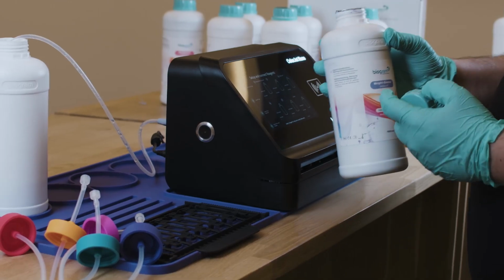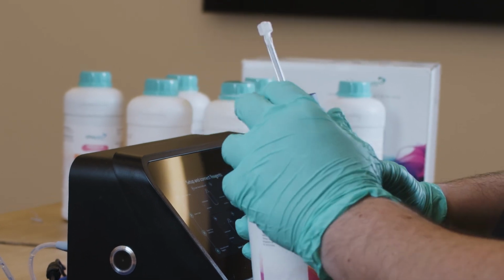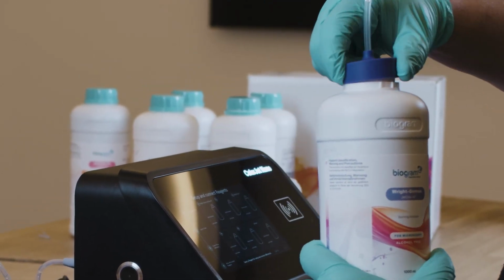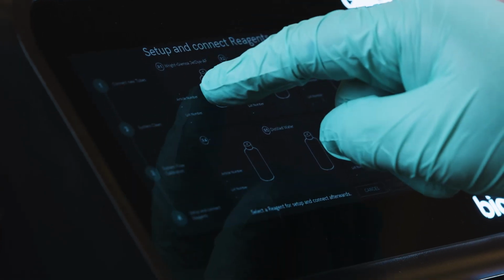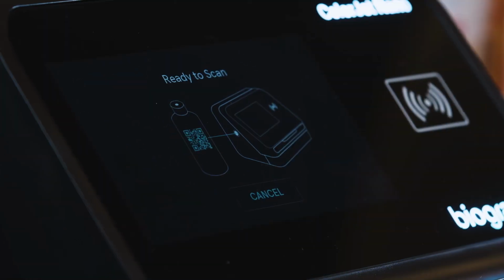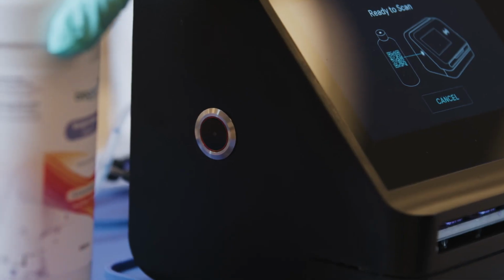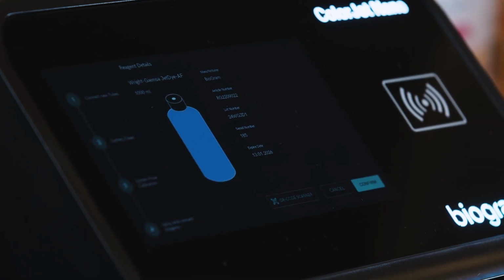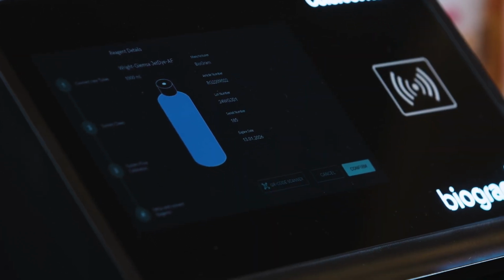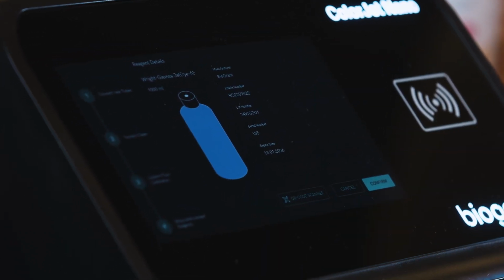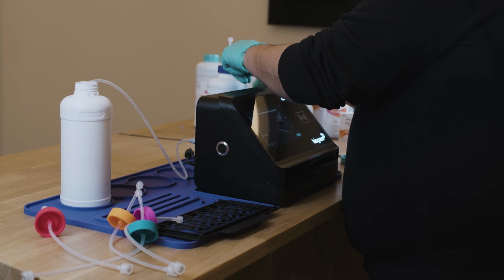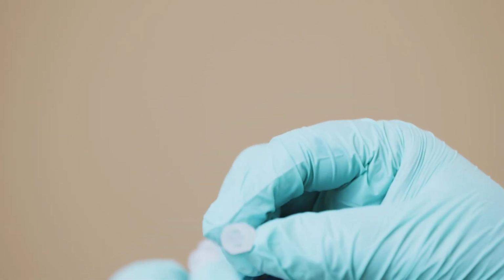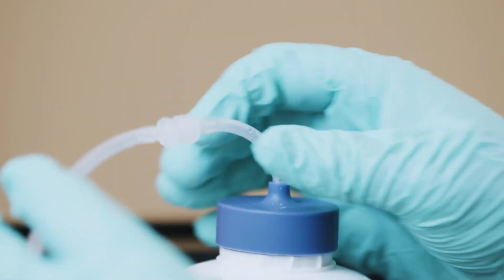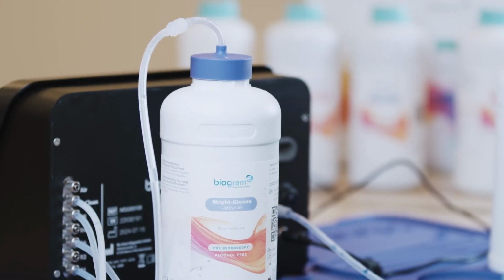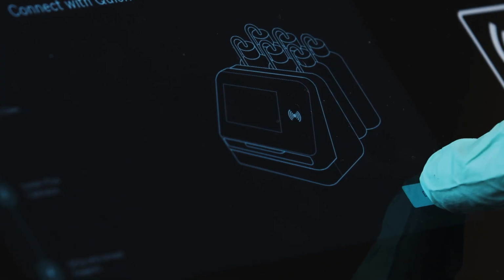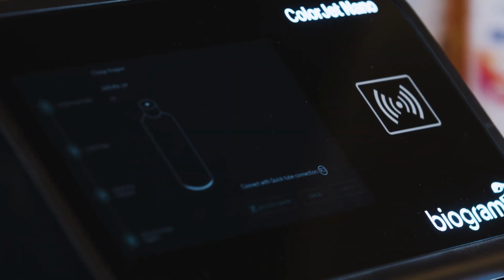Connect the selected reagent to the designated valve port, one after another, using the quick tube connector as shown on the display. Scan the QR code on each reagent using the scanner on the left side of the device. The filling volume, lot number, and expiry date will be automatically transferred to the system after confirmation. After a successful scan of the reagent, connect the Luer lock connectors and place the reagent bottle at the back of the device. Repeat for all necessary reagents.